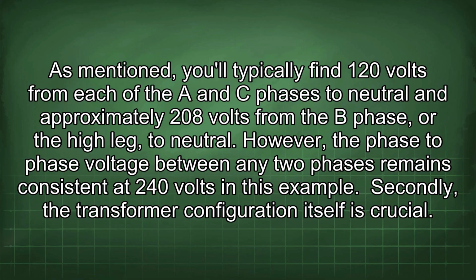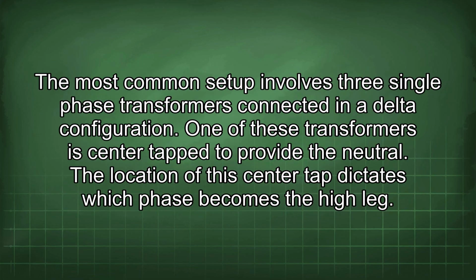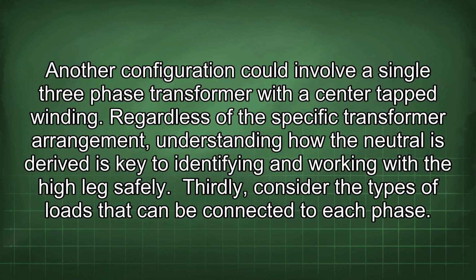Secondly, the transformer configuration itself is crucial. The most common setup involves three single-phase transformers connected in a delta configuration. One of these transformers is center tapped to provide the neutral. The location of the center tap dictates which phase becomes the high leg. Another configuration could involve a single three-phase transformer with the center tapped winding. Regardless of the specific transformer arrangement, understanding how the neutral is derived is key to identifying and working with the high leg safely.